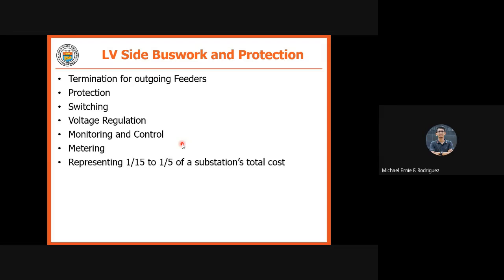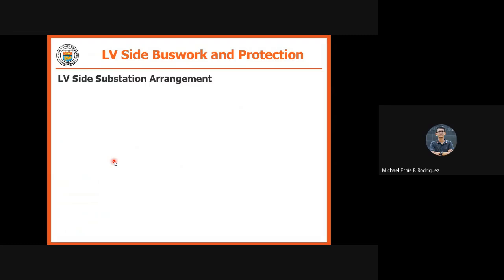The low voltage side buswork is a relatively small percentage of the cost. That is only 1/15 to 1/5 of the substation's total cost. Very low compared to the HV side buswork, because the high voltage side buswork and protection is expensive since it is high voltage. The cost of equipment at high voltages is really higher compared to low voltages. So our low voltage buswork and protection is cheap. So we have the LV side substation arrangement.